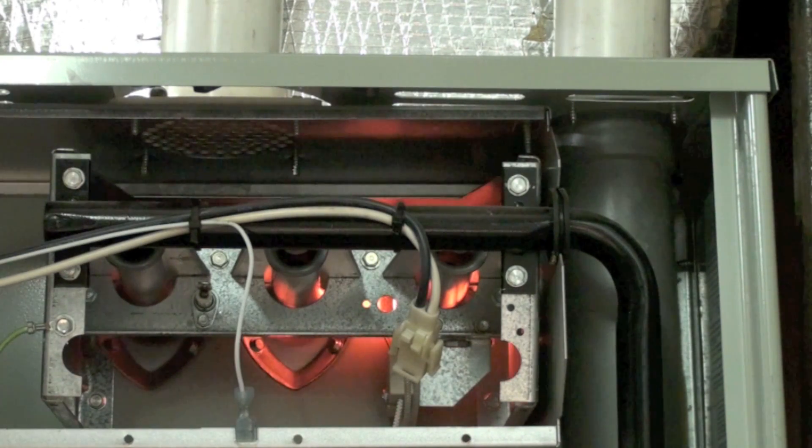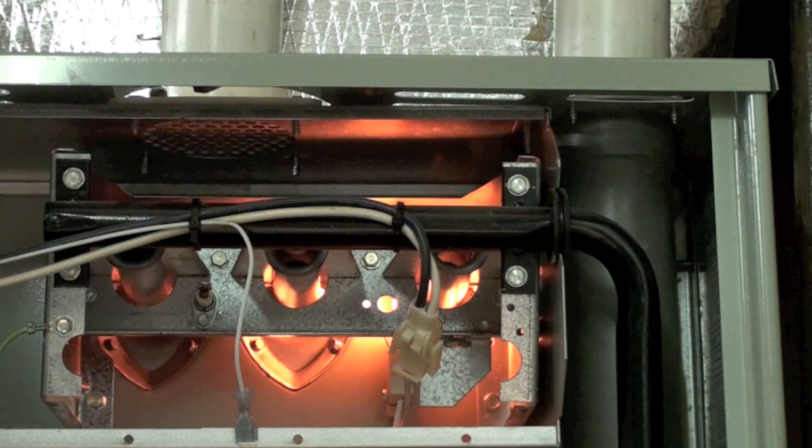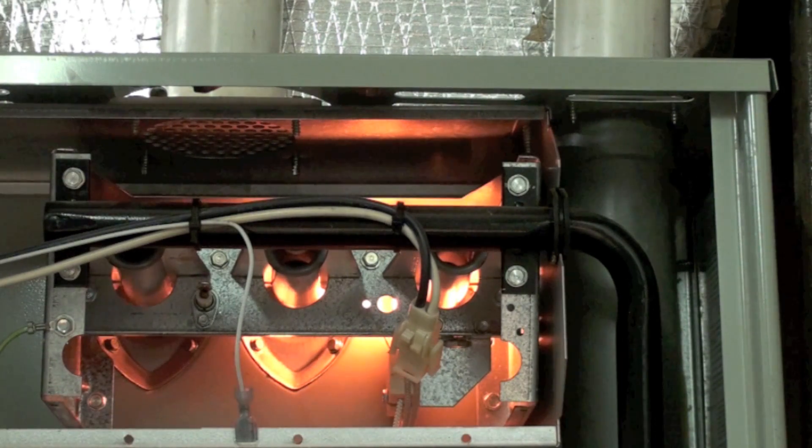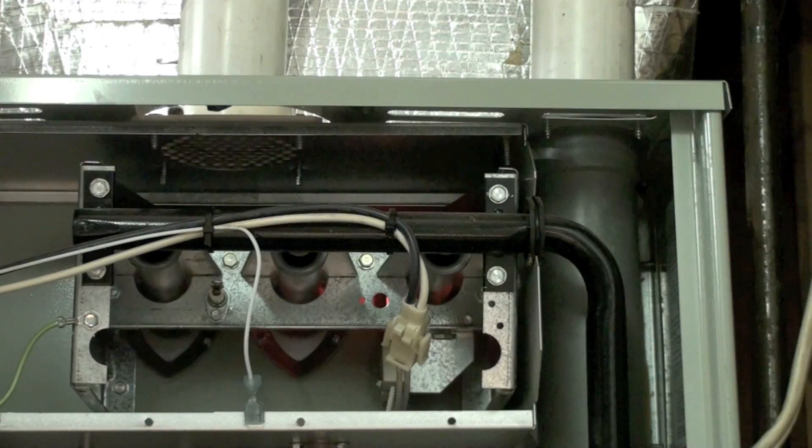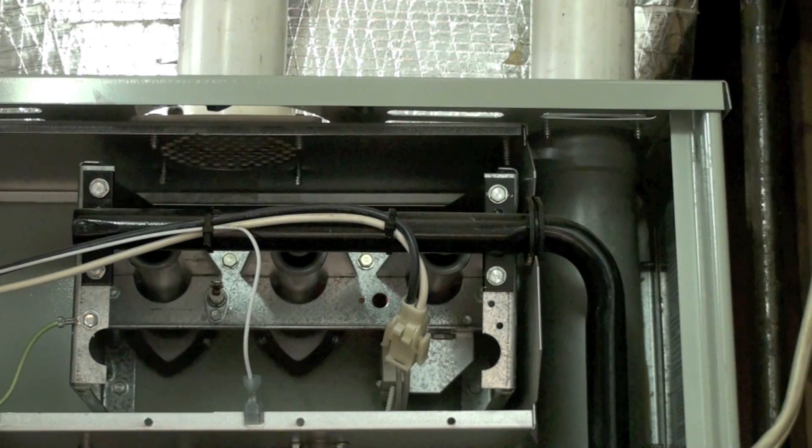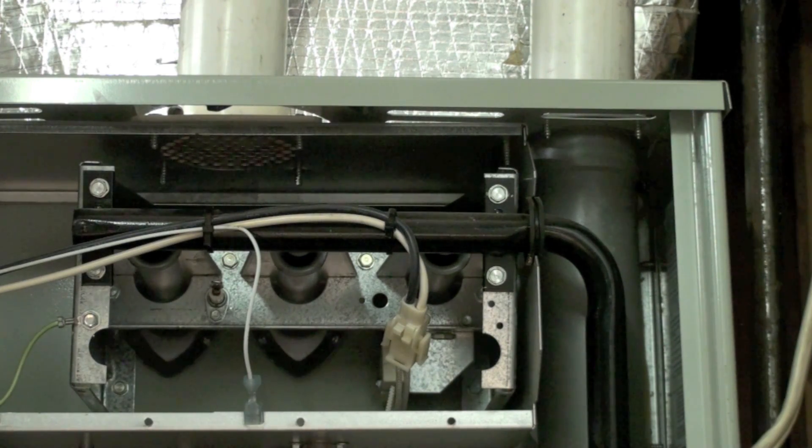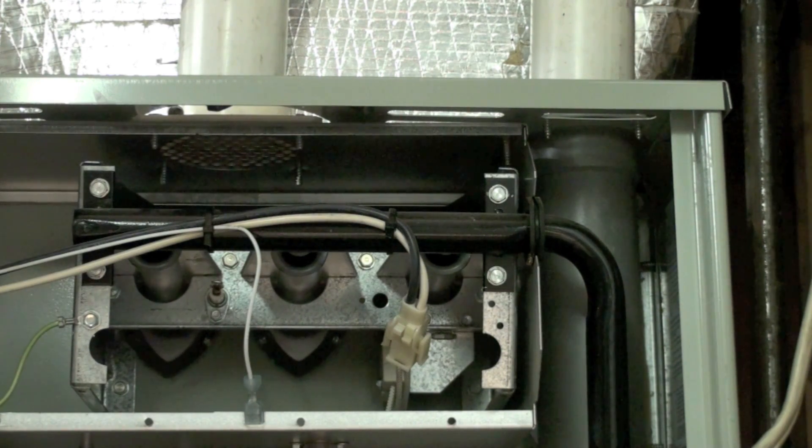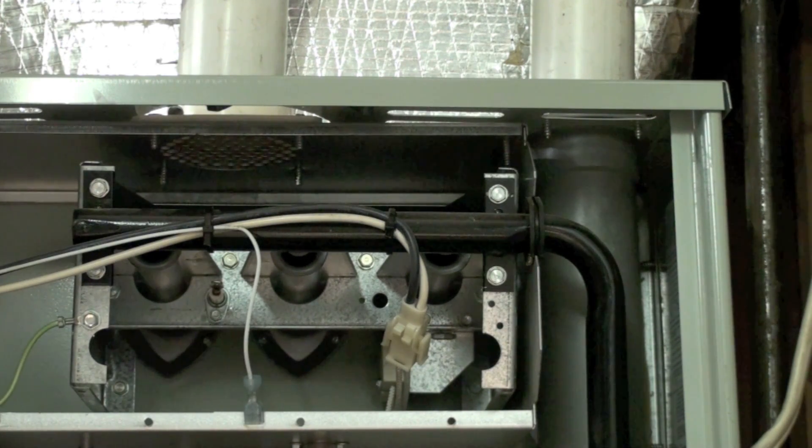Now the burners have shut off. The hot surface igniter is coming on again. It's acting as though it did not sense flame. Now it's going to try three times and then it's going to shut down. Soon as this thing shuts down, we'll pull that flame rod out of there and take a look at it and see what it is.